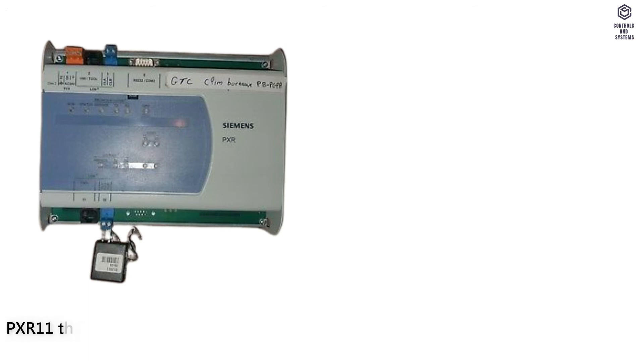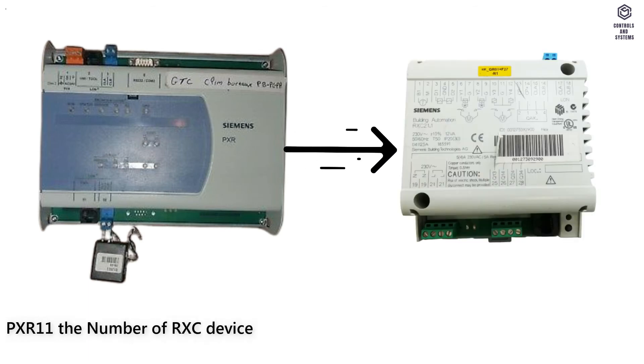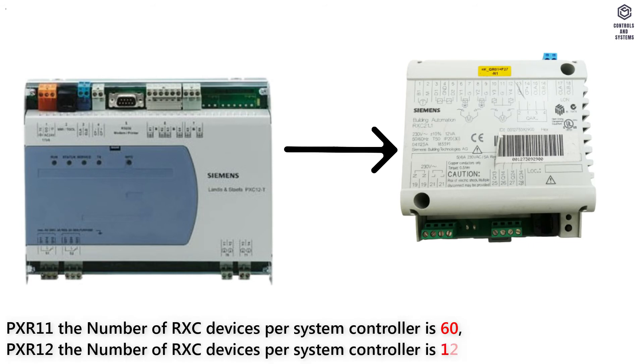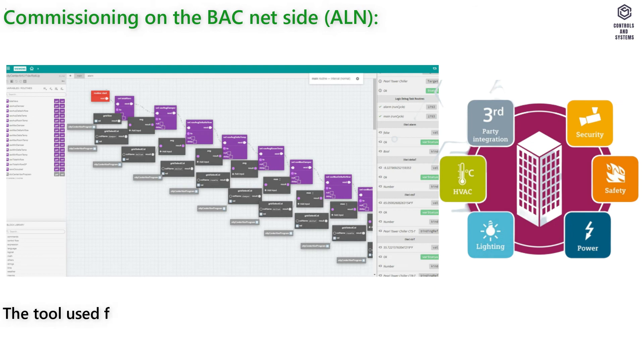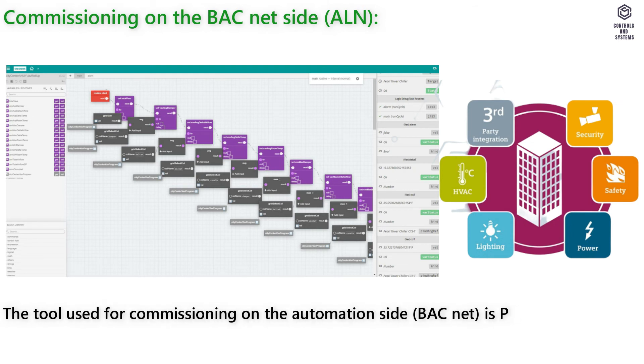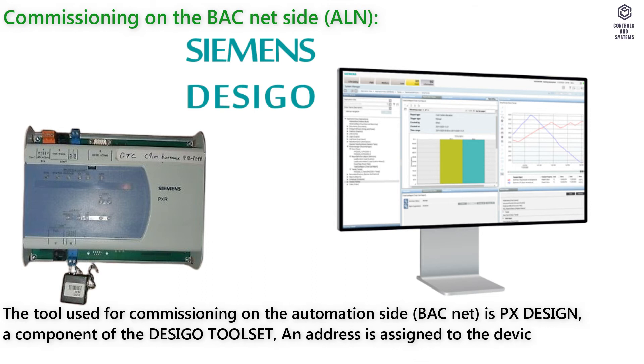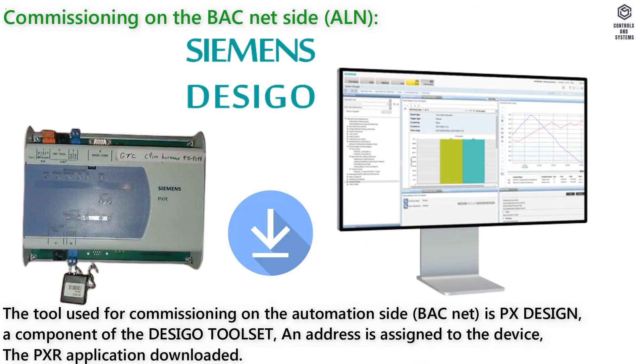Types: PXR11 supports up to 60 RXC devices per system controller; PXR12 supports up to 120 RXC devices per system controller. Commissioning on the BACnet side — the tool used for commissioning on the automation level BACnet is PXDesign, a component of the Desigo toolset. An address is assigned to the device and the PXR application is downloaded.